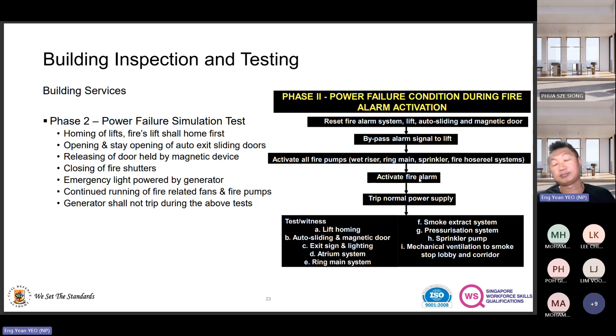The QP will go around and check all these various systems and how they react in that power outage situation. When it comes to power outage, we also want to make sure the genset kicks in - within 15 seconds normal power should be restored, the genset is supposed to kick in within that time. But the change from normal supply to UPS to battery pack is probably not more than a second.